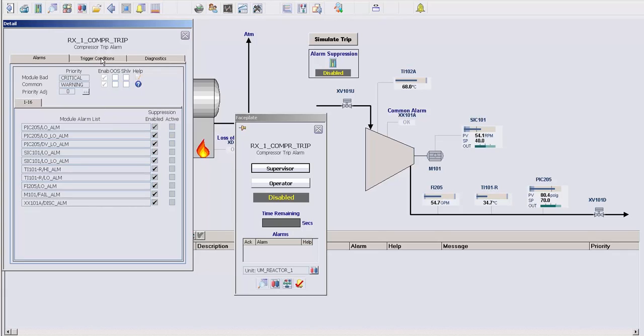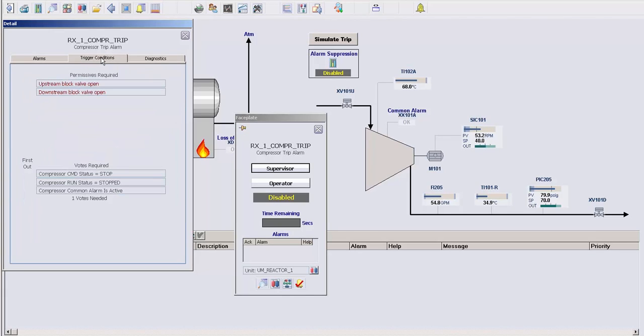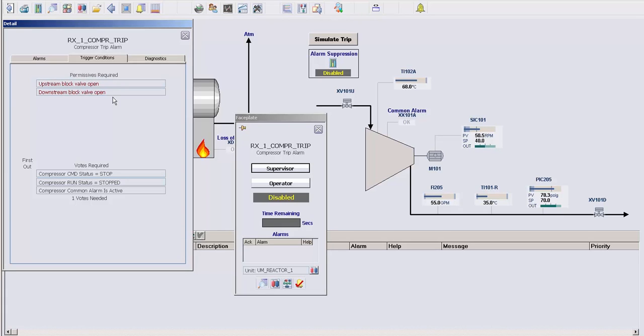You'll notice that we also have an additional tab with the label Trigger Conditions. In here, we can specify two additional pieces of logic. One, you can define some permissives for triggering the alarm suppression, in addition to the buttons to arm and disarm the logic.